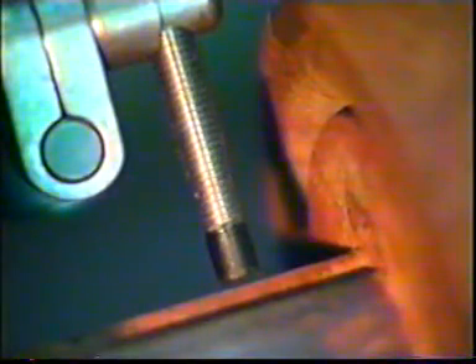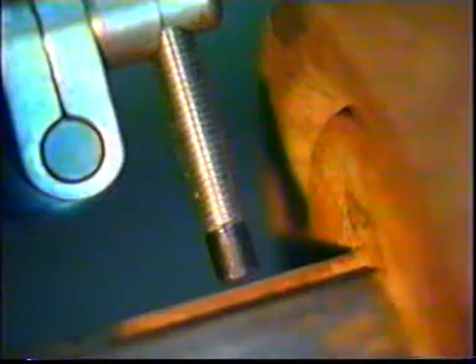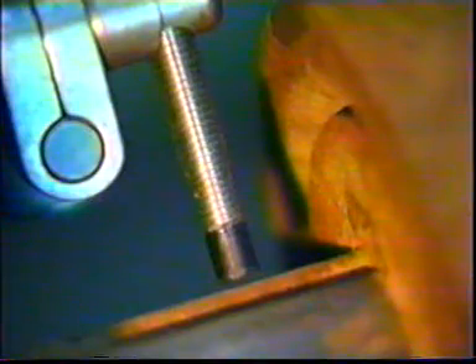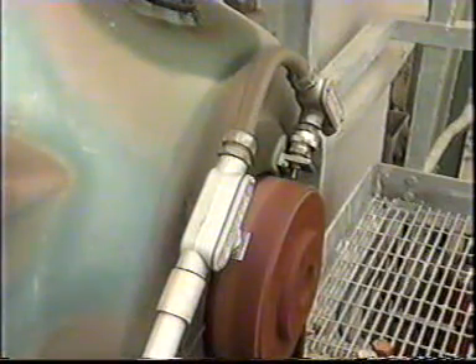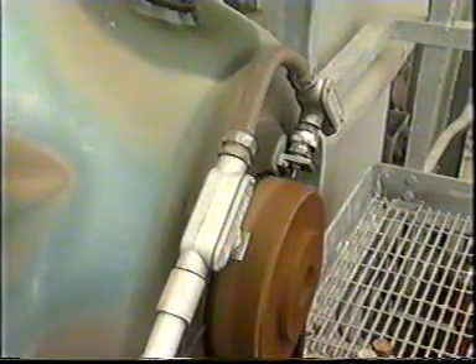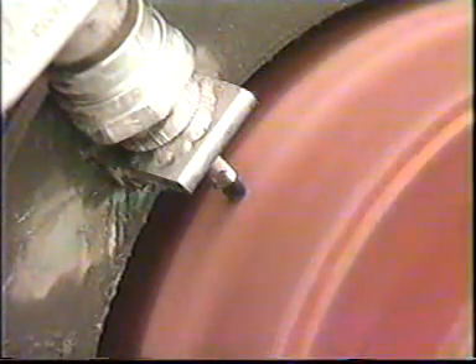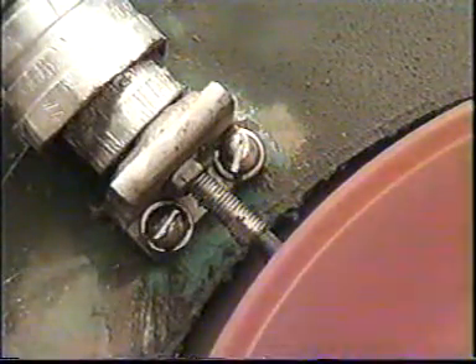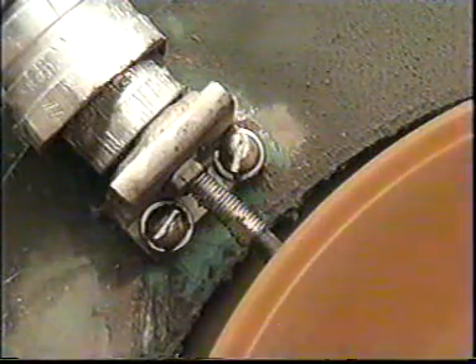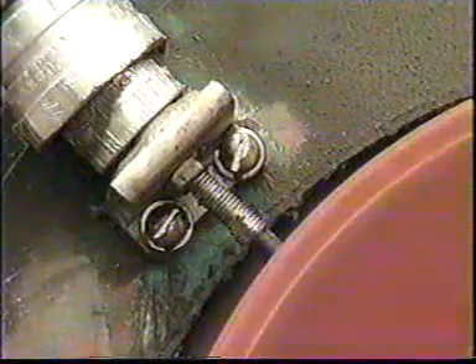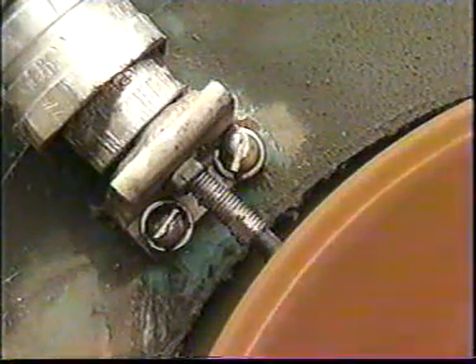Because the proximity probe uses an electromagnetic field to measure the vibration, the probe must be close enough to interact within the linear range. It is critical to follow manufacturer's installation instructions. Also, there must be enough target surface for the probe to interact. Usually, the minimum target area is a multiple of the tip diameter. Attention to mounting brackets is another consideration for proximity probes. Brackets should have at least 2 fasteners to prevent the bracket from twisting. It's important that the bracket remain in proper alignment with the shaft for accurate readings.